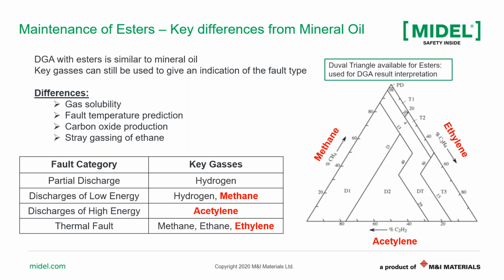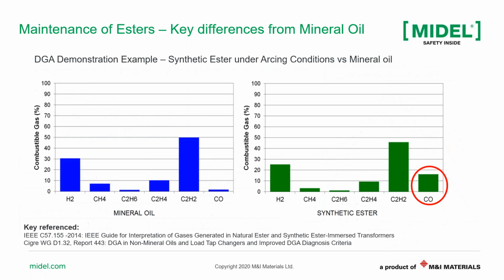So the Duval triangle basically relies on the percentages of methane, ethylene, and acetylene in this geometric presentation. And once you take the DGA and plot it here, you can guess what kind of fault in the transformer is causing these gases. So this is the DGA, and I thought to share with you one example of lab test results, where you can see on the left-hand side is mineral oil, and the right-hand side is a synthetic ester.